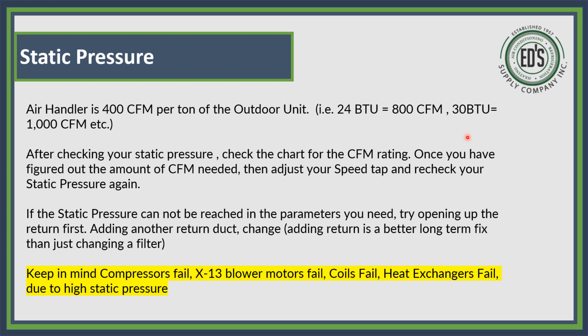After checking your static pressure, check the chart for the CFM rating. Once you have figured out the amount of CFM needed, adjust your speed tap and recheck your static pressure again. If the static pressure cannot be reached within the parameters you need, try opening up the return first, which means make a bigger return grill or maybe add a return grill. Adding a return is a better long-term fix than just changing out a filter.